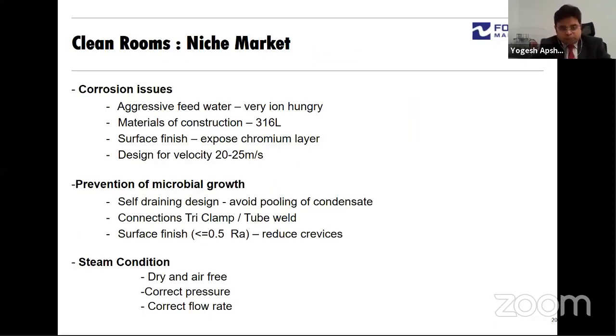We do the system and the component design with these aspects. If you see clean rooms, this is a very niche market. These are very special requirements. There are corrosion issues because the water which we are using is purified water or WFI, which is very ion hungry. The material of construction has to be 316L. For the surface finish, we have to expose the chromium layer, otherwise the material will be eaten by the steam. Then the prevention of microbial growth. The designs have to be self-draining to avoid any condensate clogging. The surface finish has to be less than or equal to 0.5 microns Ra. And the steam has to be dry and air-free, with the correct pressure and correct flow rate.